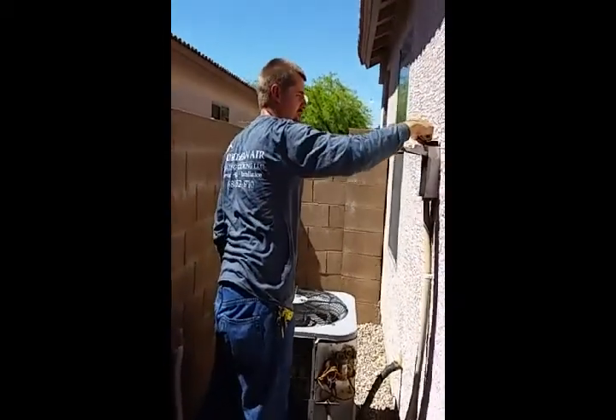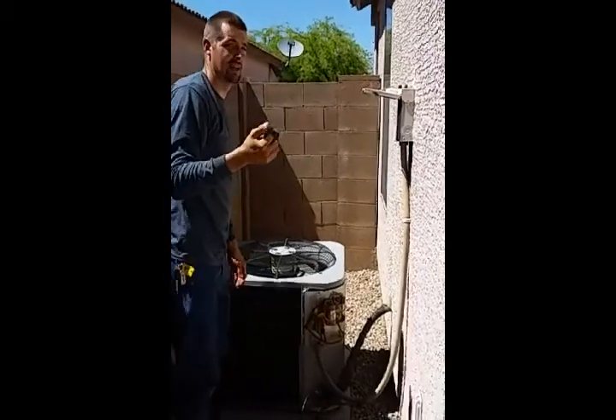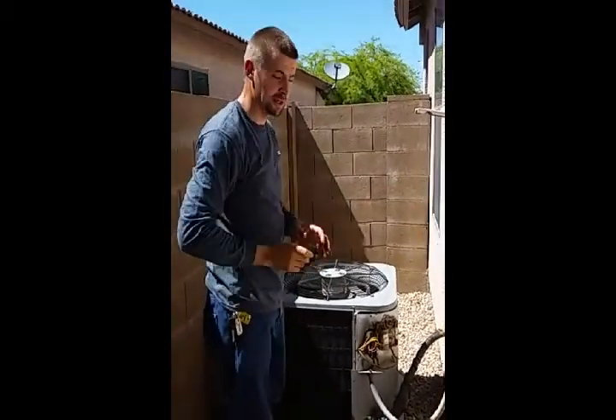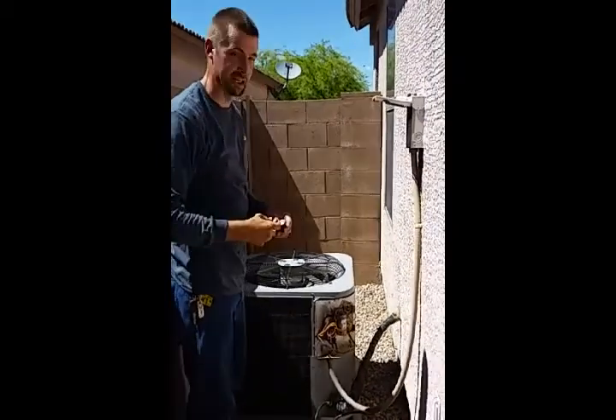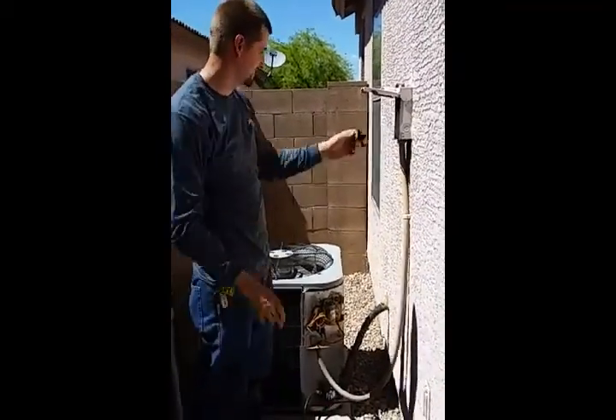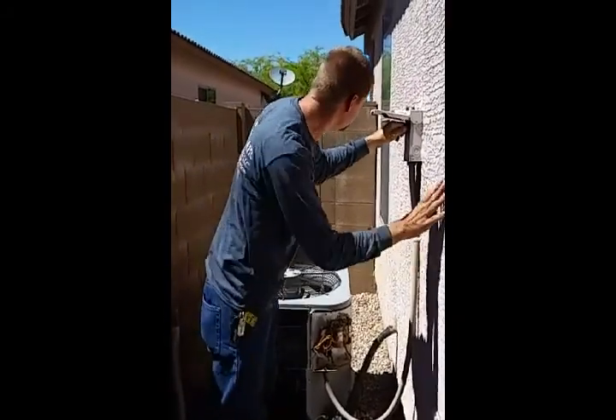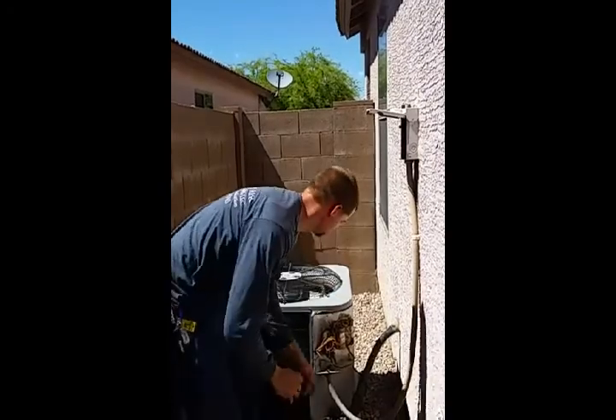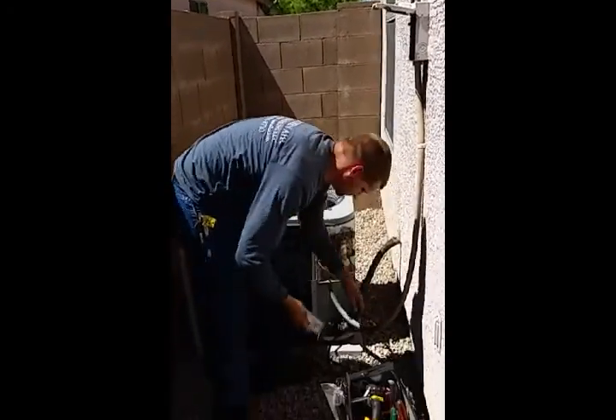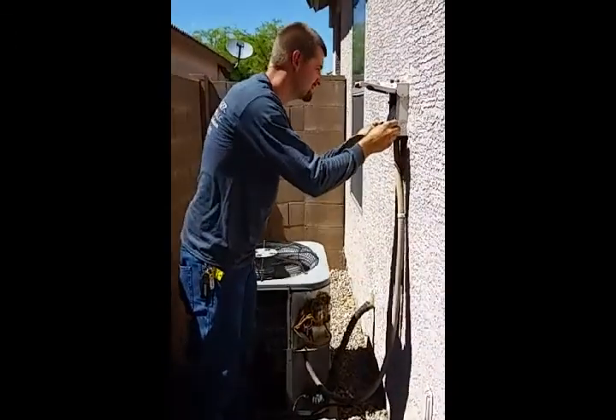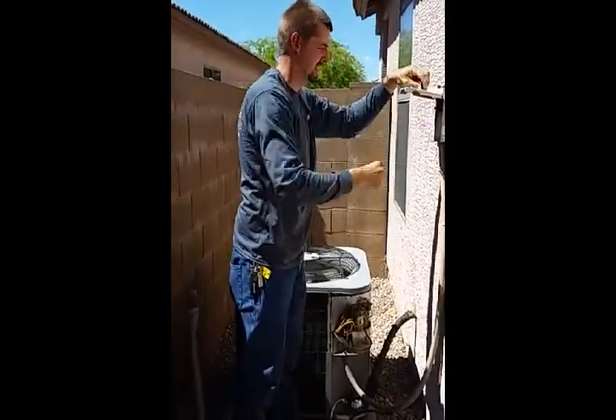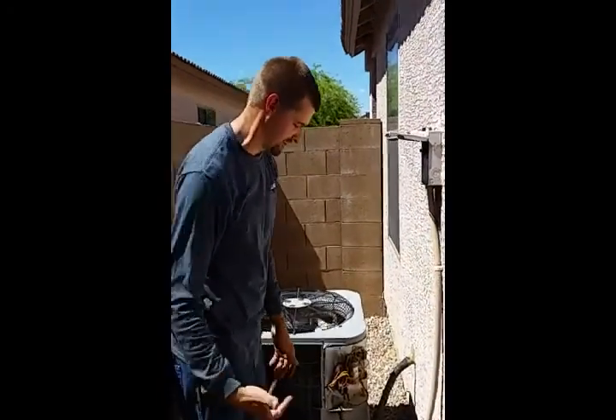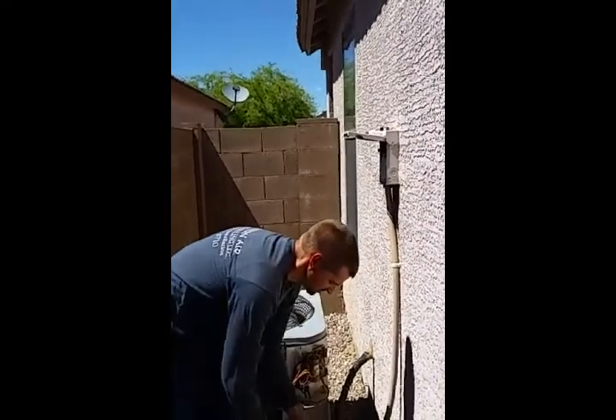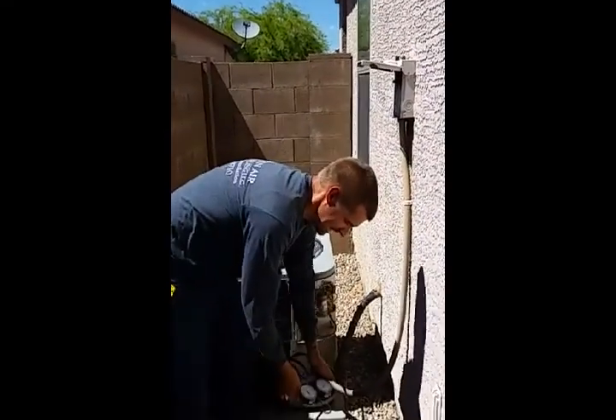Now what I would usually do is plug in the disconnect and let it run for about 10 to 15 minutes. Let the pressures equalize, let my superheat readings stabilize as well. So I will plug this in. Usually let it run for about 10 to 15 minutes. But in this case, we're going to let it run for about, I would say, 2-3 minutes, let it stabilize, and then check it.